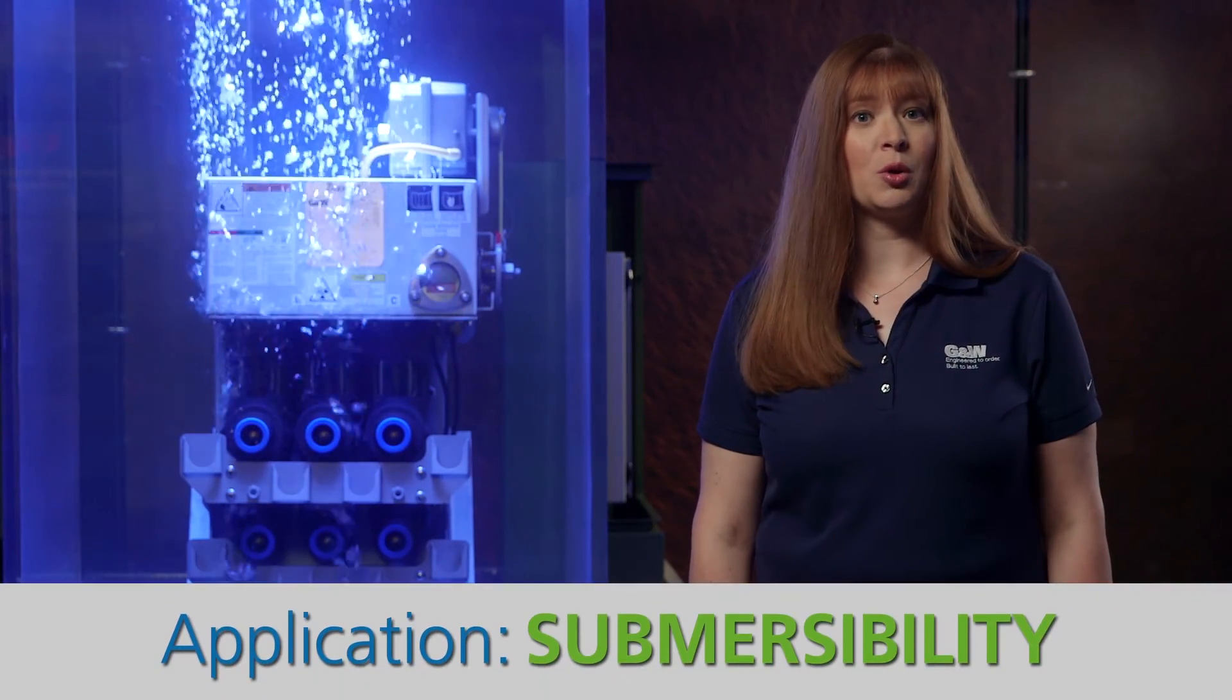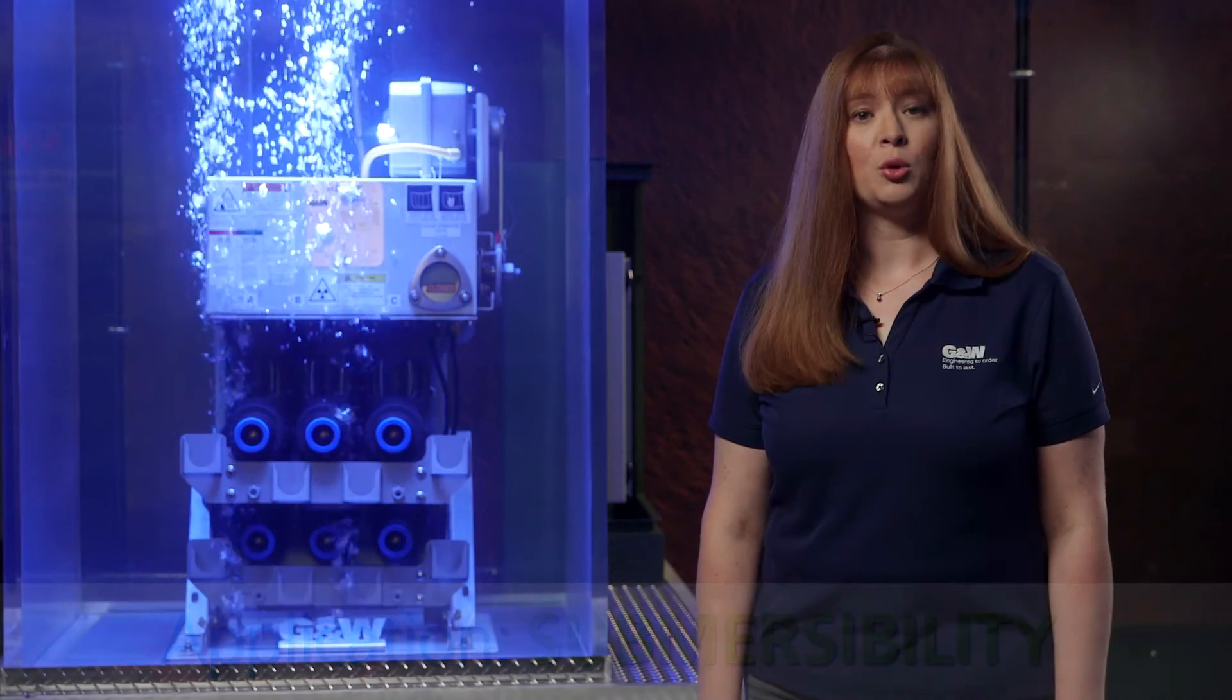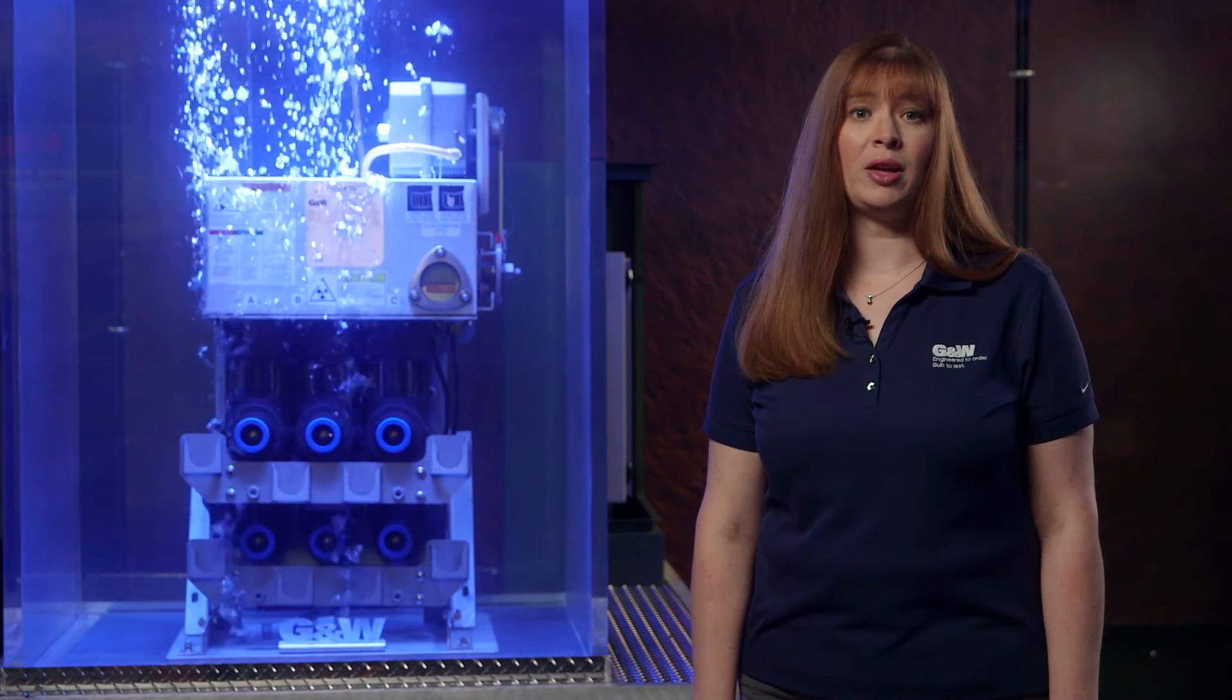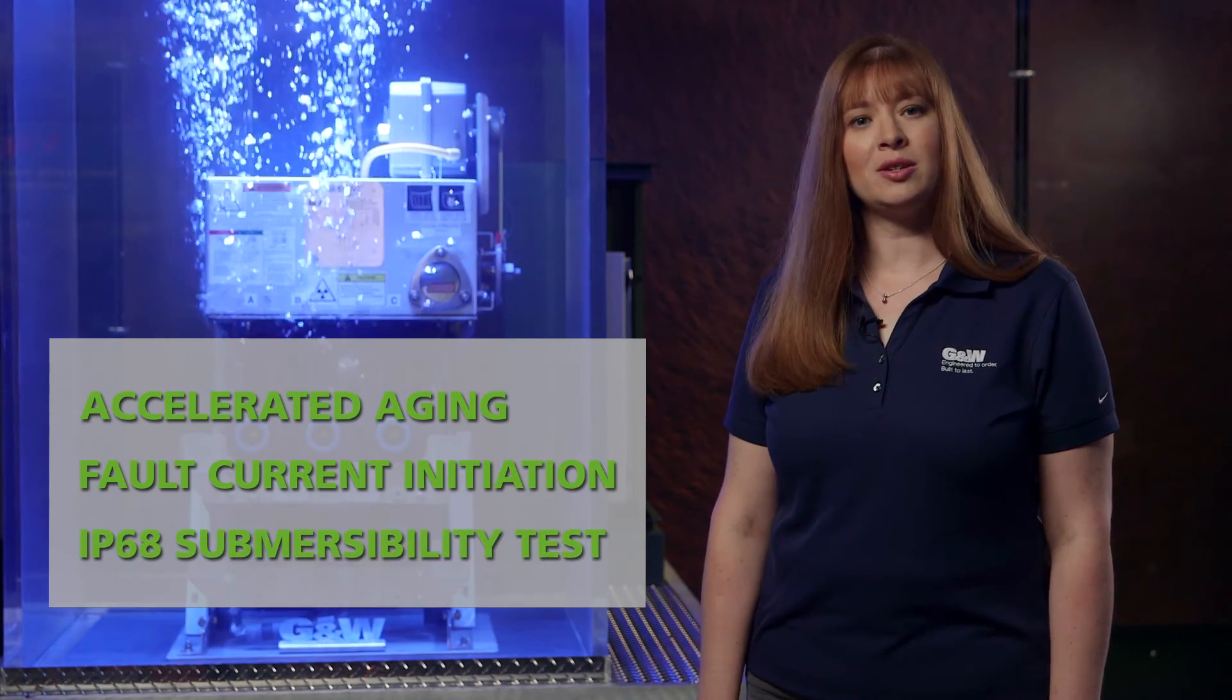Some applications require the equipment to be submerged for an extended period of time. With that in mind, Trident with SafeView switches are tested above and beyond the ANSI standards. We perform a combination of accelerated aging, fault current initiation, and IP68 submersibility test to ensure the product will function correctly in the harshest environments.